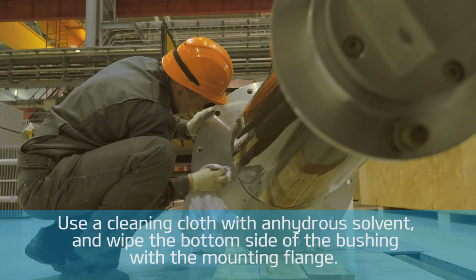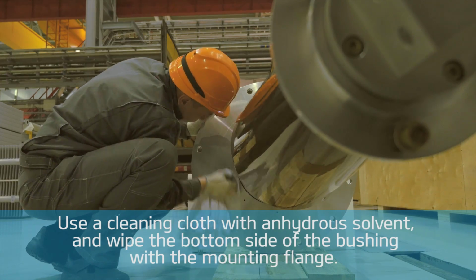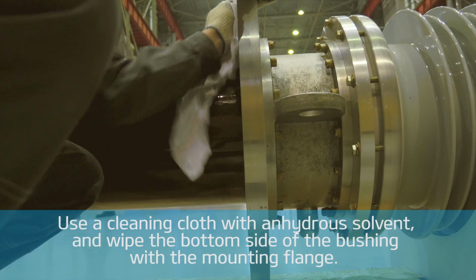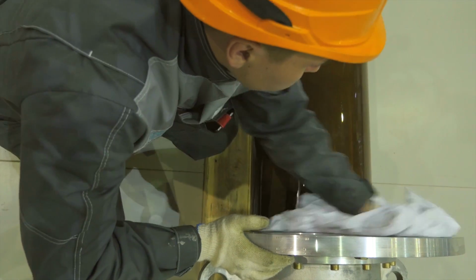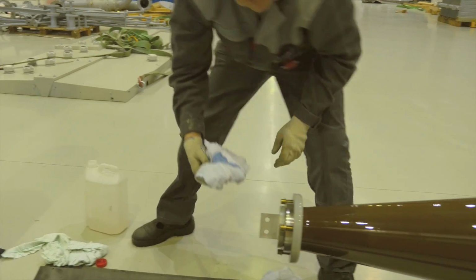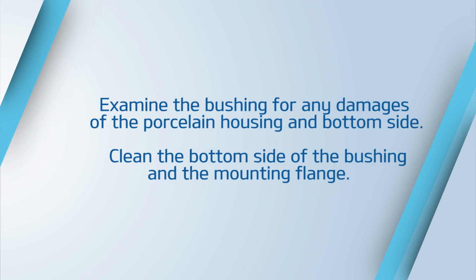Use a cleaning cloth with anhydrous solvent and wipe the bottom side of the bushing with a mounting flange. This procedure is to be done before the internal insulation properties check in order to receive reliable measurements. Thus, we have examined the bushing. So let us review the most important points. Examine the bushing for any damages of the porcelain housing and bottom side. Clean the bottom side of the bushing and the mounting flange.